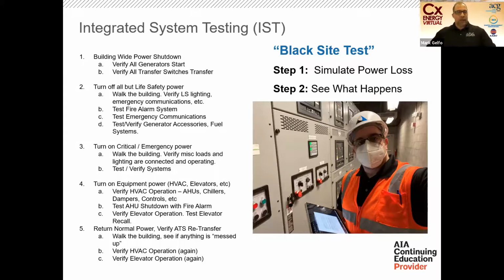We want to shut down all the power and simulate the power loss, watch the generator start, watch the transfer switches transfer, make sure that works. And then basically, the way I like to do it, turn off everything else except the life safety, except that emergency power, emergency branch, that most critical branch, most important branch.